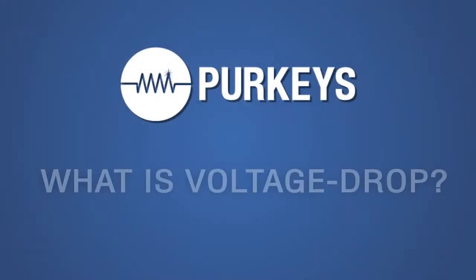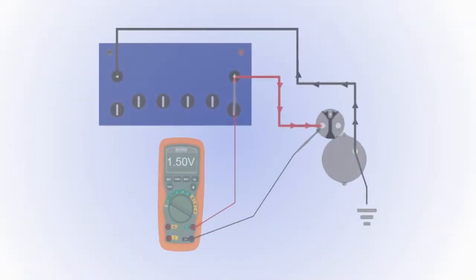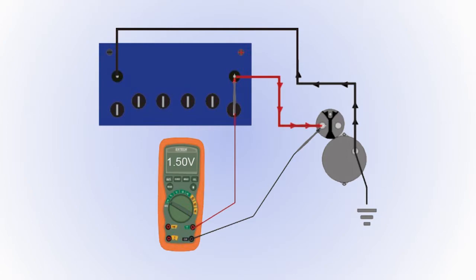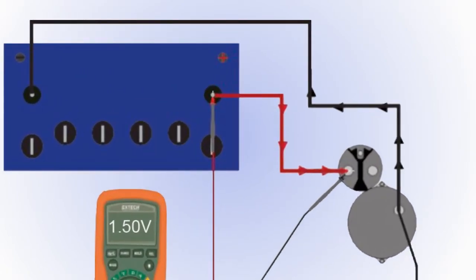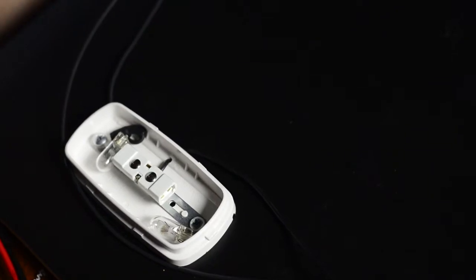When we talk about voltage drop, first we probably ought to make sure we understand what voltage drop means. A voltmeter only reads a difference between two different points. So if I look here, I have zero—this is my absolute zero. When I put my other lead here, all it's going to do is display the difference or however much voltage was lost between these two points.